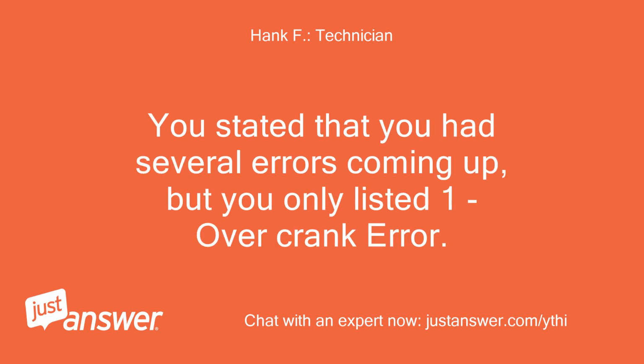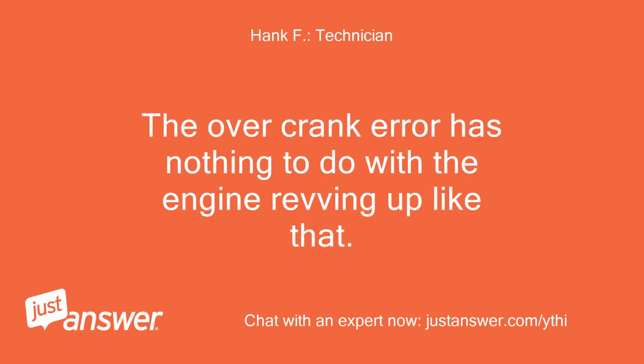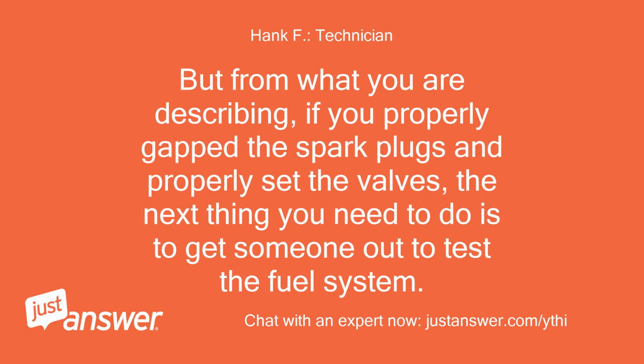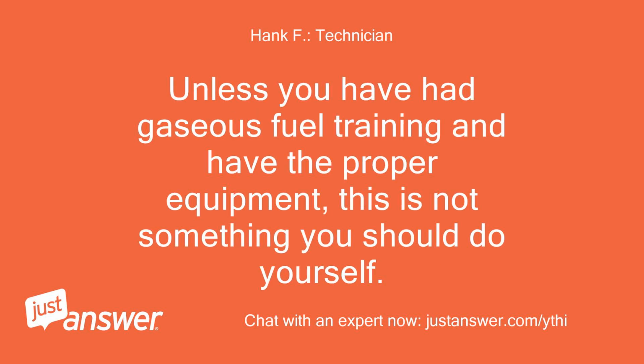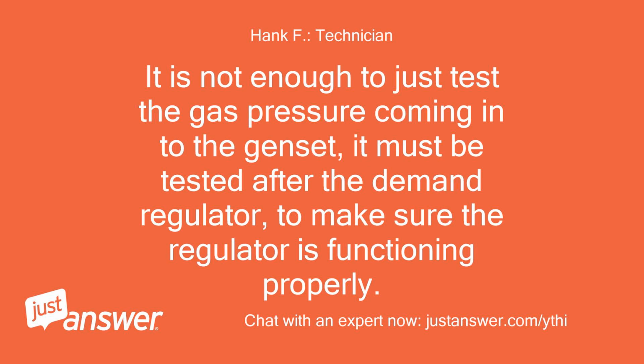You stated that you had several errors coming up, but you only listed one, overcrank error. The overcrank error has nothing to do with the engine revving up like that. But from what you are describing, if you properly gap the spark plugs and properly set the valves, the next thing you need to do is to get someone out to test the fuel system. Unless you have had gaseous fuel training and have the proper equipment, this is not something you should do yourself. It is not enough to just test the gas pressure coming into the genset, it must be tested after the demand regulator, to make sure the regulator is functioning properly.